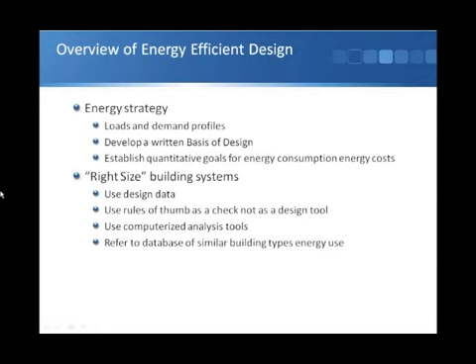If we're going for net zero energy, we really have to understand how the building functions, how much heating it actually wants. And for a modern building built to the sort of standards I'm talking about, it will not be 100 watts a square metre. In fact, you might even get to the point of asking whether you need a heating system at all. So we will see much lower heating loads with well-insulated buildings, and we might see an opportunity to heat those buildings with recovered heat rather than boiler plant.